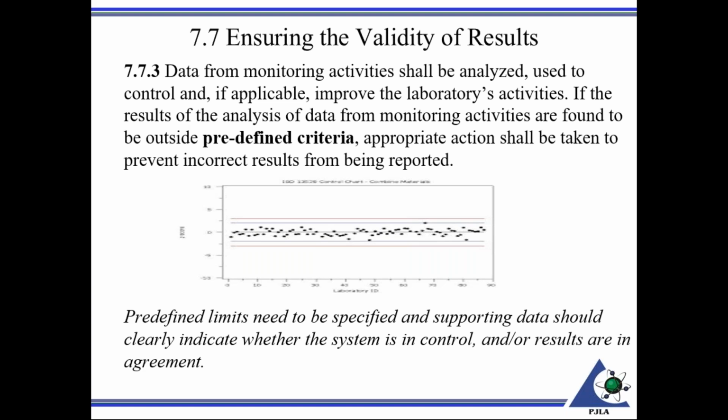So I have seen folks having logs for, let's say, a scale or a balance that's going to be used to perform a gravimetric type calibration. Put a test weight on there, record it. Ask the question, what are you looking for? You need to have an answer there as far as the predetermined criteria to determine whether or not everything is in control. Same with proficiency testing, interlab proficiency testing.